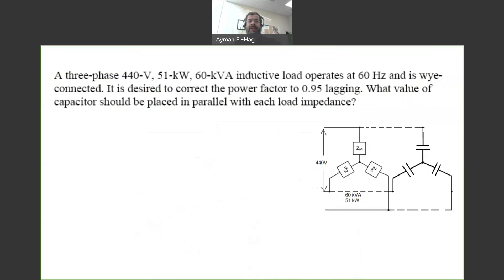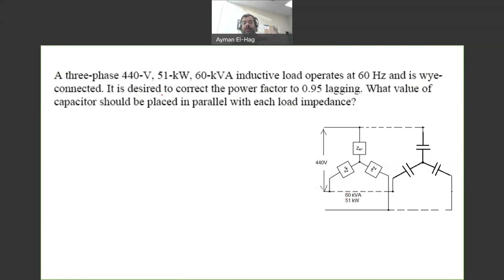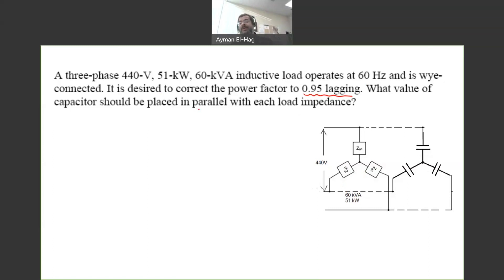Here in this question we have a three-phase 440-volt line-to-line voltage, 51 kilowatt real power, and 60 kVA apparent power. This is a load connected in Y, operating at 60 Hz. We know S and P. It is desired to improve the power factor to 0.95 lagging. To do that, we need to connect what we call a capacitor bank.